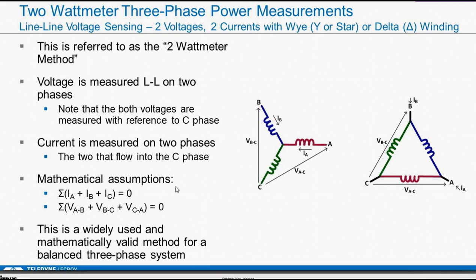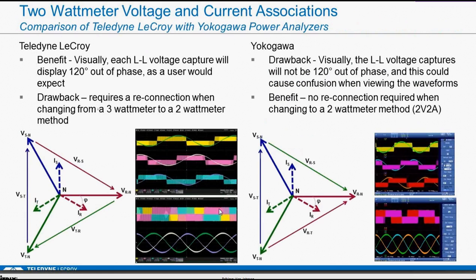All right? And then the mathematical assumption we're making here is that we have balance in our system. So the sum of all the currents is zero, and the sum of all the voltages is zero, which is what it should be if you don't have any, let's say, leakage of current to ground or something like that. So therefore, if you know two of the currents, by definition, you know the third. You can solve for it. And if you know two of the voltages, by definition, you know the third because you can solve for it using these equations. So you can use the two wattmeter method to measure three-phase power of a system. It's quite commonly used. And it's a very valid approach.